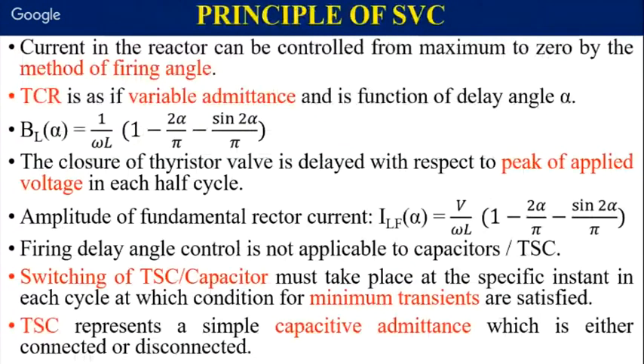So current in the reactor can be controlled from maximum to 0 by the method of firing angle. If the firing angle is 0, that means no delay. It is as if you have switched on the reactor without any delay. If you give some delay, current will be reduced because its conduction is reduced. So current carried by the reactor will reduce, which is as if it has high impedance. So it is as if introducing a high reactor in the SVC.